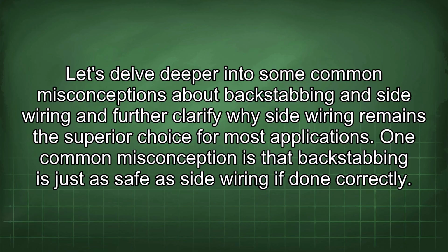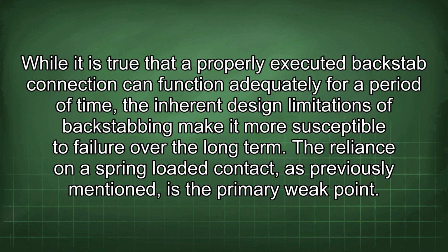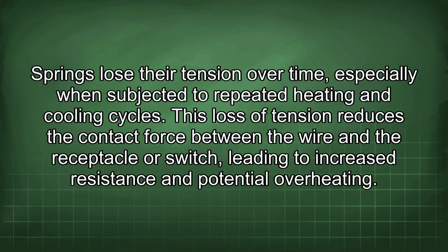One common misconception is that backstabbing is just as safe as side wiring if done correctly. While it is true that a properly executed backstab connection can function adequately for a period of time, the inherent design limitations of backstabbing make it more susceptible to failure over the long term. The reliance on a spring-loaded contact, as previously mentioned, is the primary weak point. Springs lose their tension over time, especially when subjected to repeated heating and cooling cycles. This loss of tension reduces the contact force between the wire and the receptacle or switch, leading to increased resistance and potential overheating.